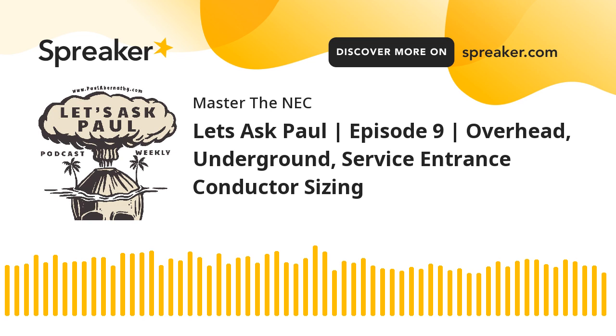Then you go back and say, okay, now I have to do a load calculation under the standard method for my grounded conductor. And then whatever size results from the VA based on my calculation, you divide that by the 240 volts or whatever you're dealing with. Then you say, okay, here's my ampacity.